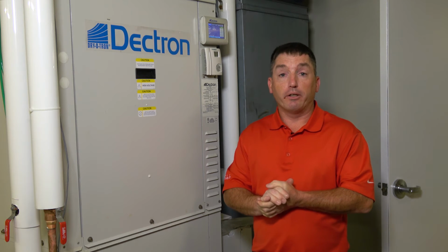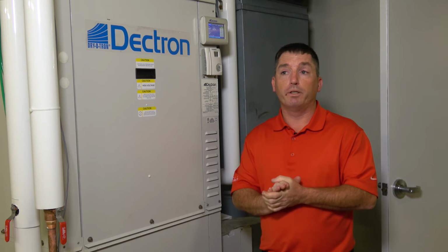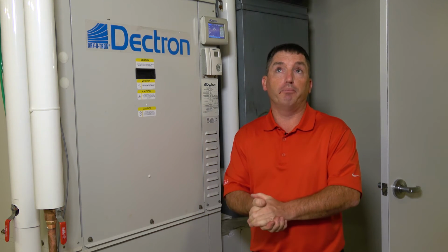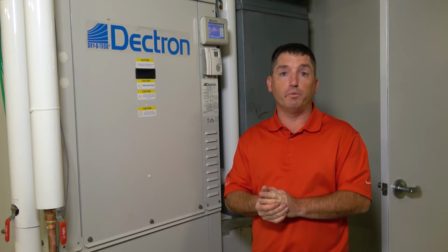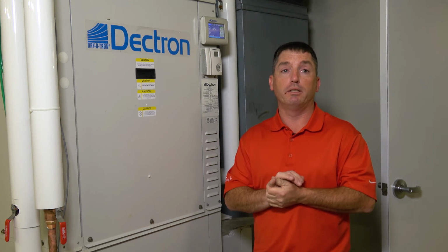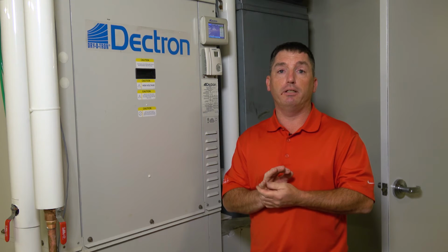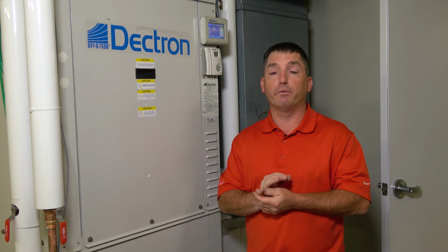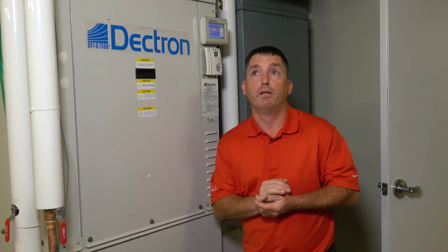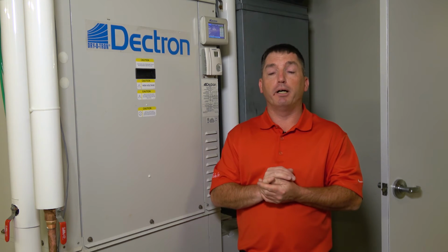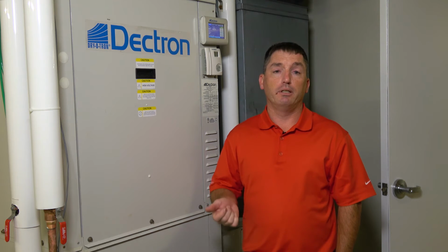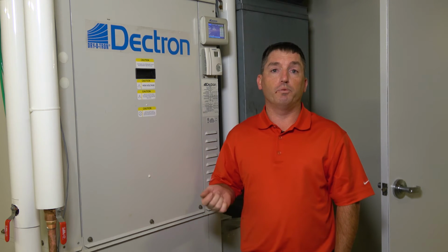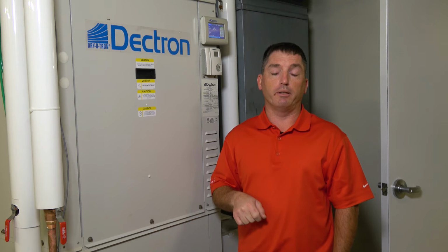Unlike your air conditioner or furnace at home, where you would adjust your temperatures when you're home versus when you're away, in a pool environment, once it is set up and at condition, we'll call it, you never change the temperature set point or the relative humidity set point. Another key thing to keep in mind is your air temperature. You want that to be 1 to 2 degrees warmer than your pool water temperature.